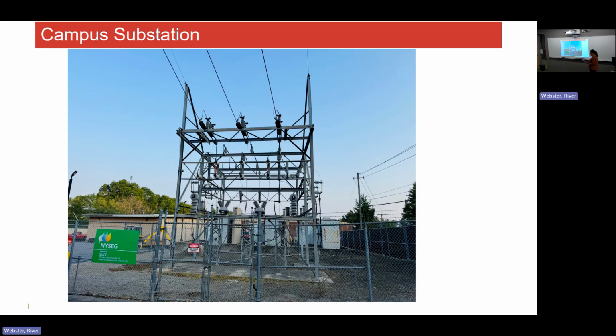Our campus is a radial system with 5 feeders, with 2 redundant feeds at each building. There's bus 100, 200, and 300. 2 feeds come out of this one, 2 out of this one, and I don't know why one only has 1. So we have 5 feeds that come out, and then into each building you would have a combination.